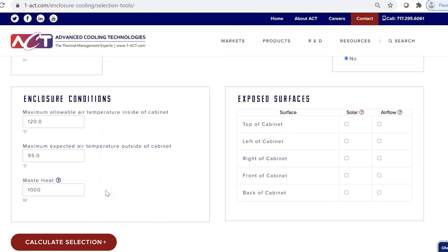Solar loading works as it sounds — if you have a delta T and sun coming down, it's going to add heat into your system. The suggestion is to use two adjacent surfaces, which gives a good approximation for an outdoor environment. In this case, the top and left surfaces are subject to solar loading. For airflow, any surface available for free convection can add or subtract heat from your system depending on the delta T. Here, the back surface does not get free convection, but all other surfaces do.